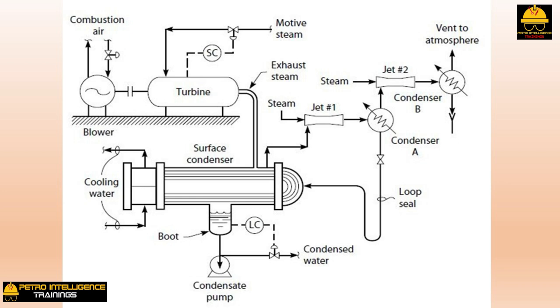For a surface condenser to work properly, non-condensable vapors must be sucked out of the shell side using a two-stage jet system. When the jets were first commissioned, they were unable to pull a good vacuum; moreover, water periodically blew out of the atmospheric vent. After considerable investigation, it was found that the condensate drain line from the final condenser was plugged. The maintenance crew disassembled and cleaned the drain lines but failed to reassemble the loop seal from condenser A.